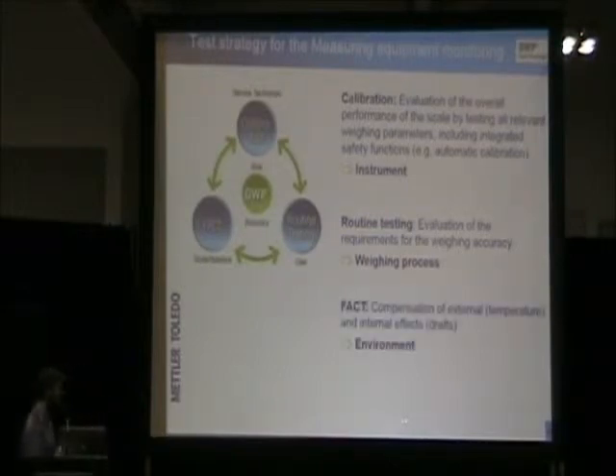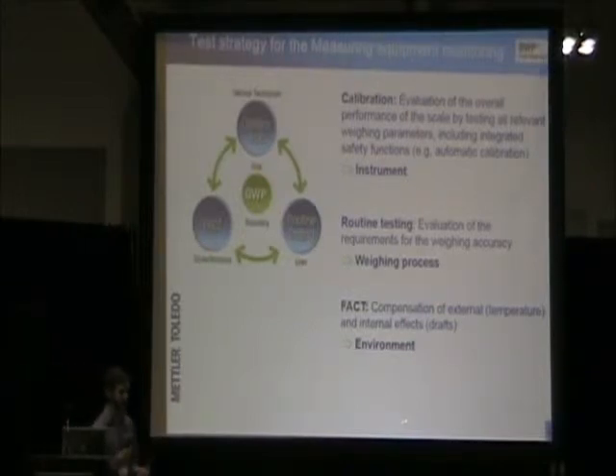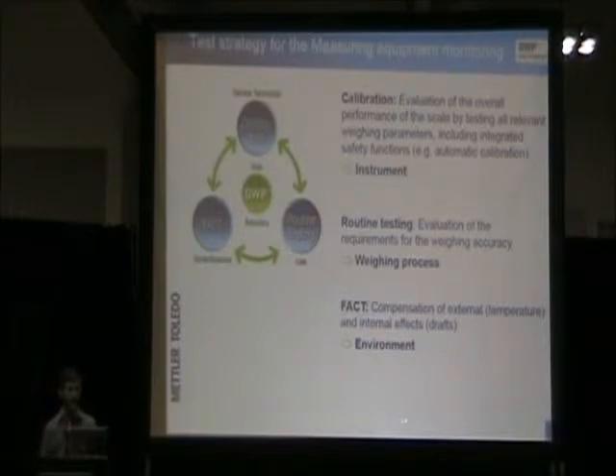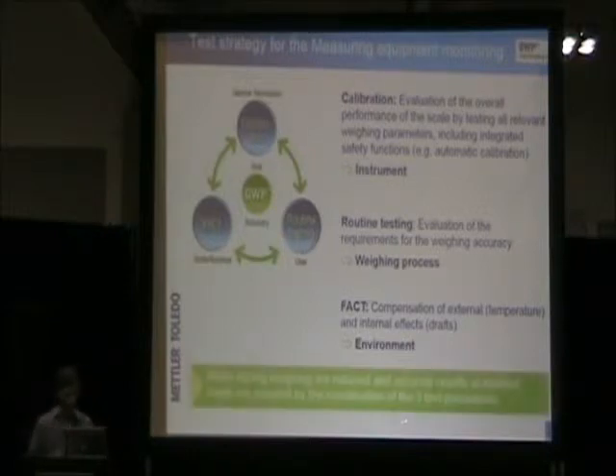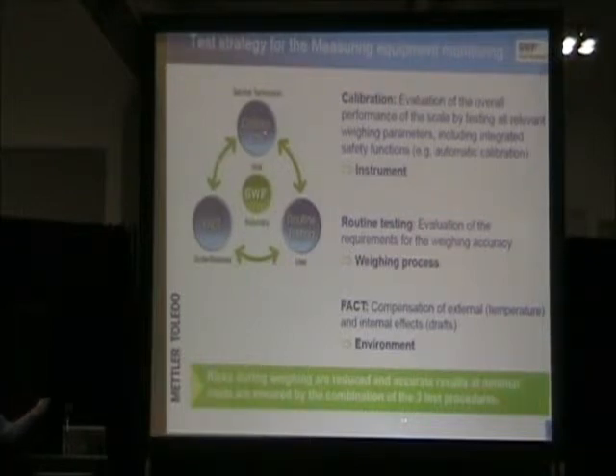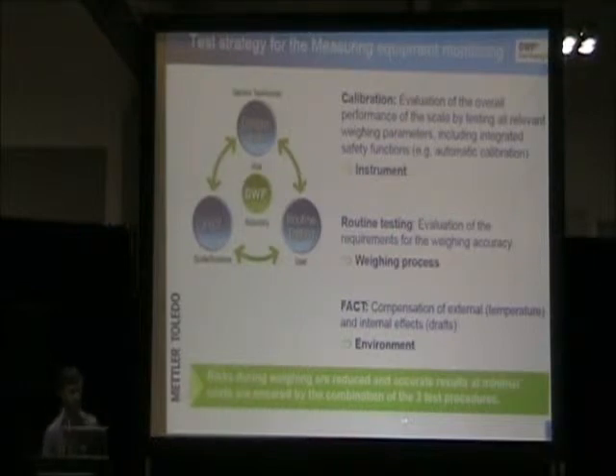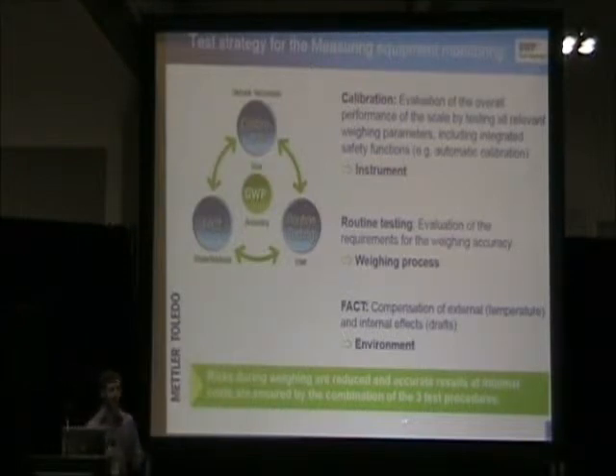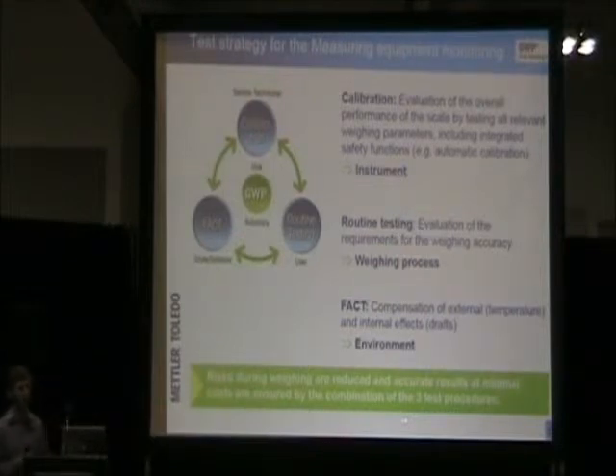And then you have the internal system of your instrument that is performing an internal adjustment, whether it's based off of a time schedule, or in the case of Mettler-Toledo weighing instrumentation, you can have it set so that it will kick in if there's a difference of temperature of a certain value that you set. So, as you're weighing throughout the year, by making sure you're getting your instruments properly serviced, by doing adequate routine testing, and by allowing your instrumentation to perform the type of internal adjustment it's capable of, you'll be ensuring that your balances are as accurate as possible throughout their entire lifespan and in between your calibration times.